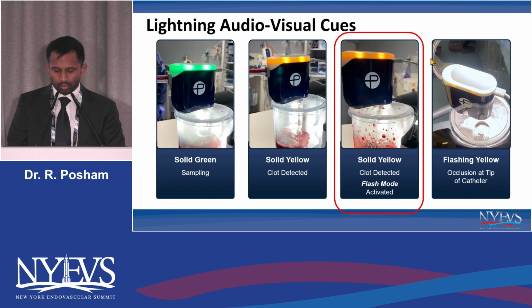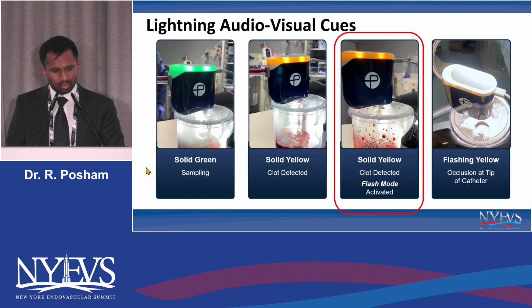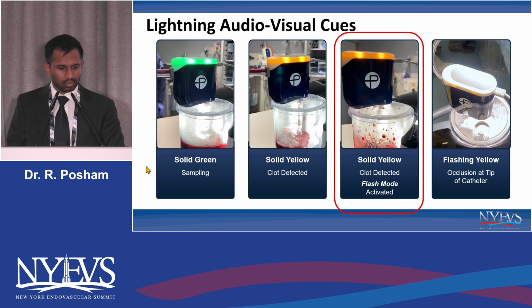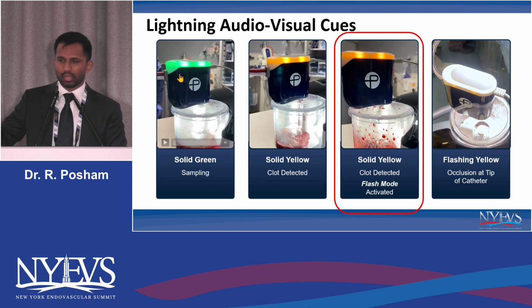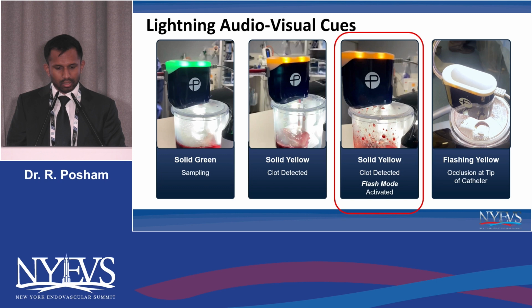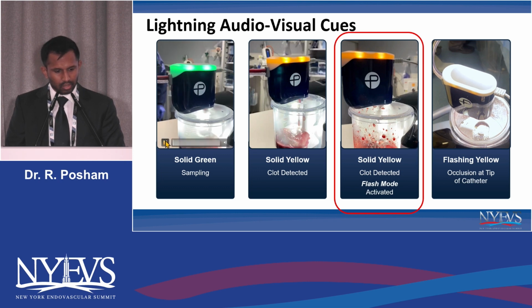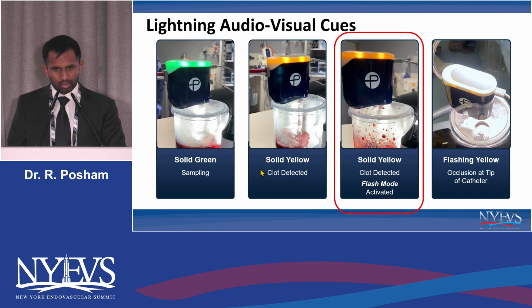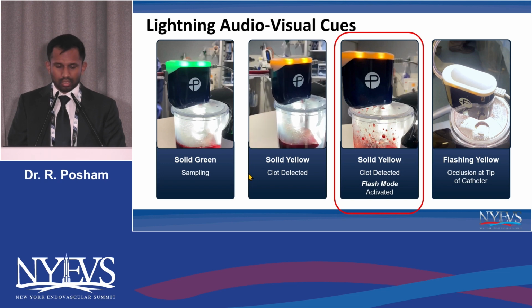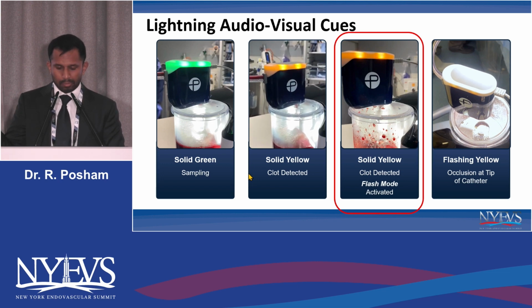So I'm just going to go through the way that this device works when you're operating it. I think there should be audio on this slide, but if there's not, when it's green, you just hear clicking about 1 second at a time. And at that time, it's sampling about 0.3 cc's of blood per second. There you go.